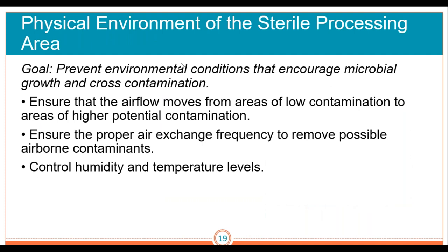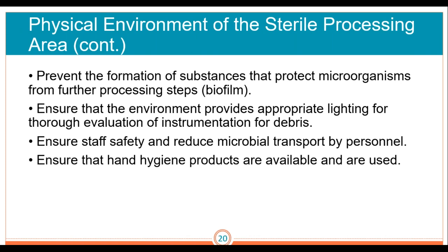Physical environment of a sterile processing area: our goal is to prevent environmental conditions that encourage microbial growth and cross-contamination. We want airflow moving from areas of low contamination to areas of higher potential contamination, ensure proper air exchange frequency to remove airborne contaminants, and control humidity and temperature levels. Your decontam, clean assembly, and storage areas all require certain temperature and humidity parameters that you need to know for your test.